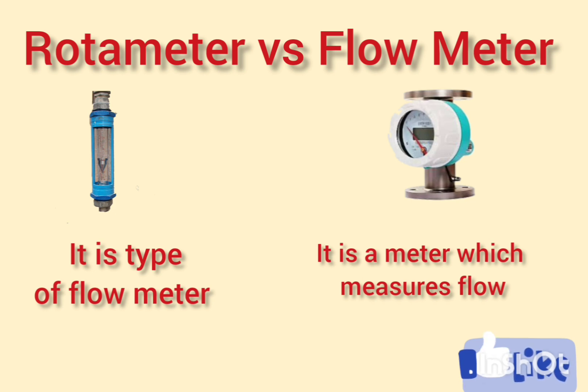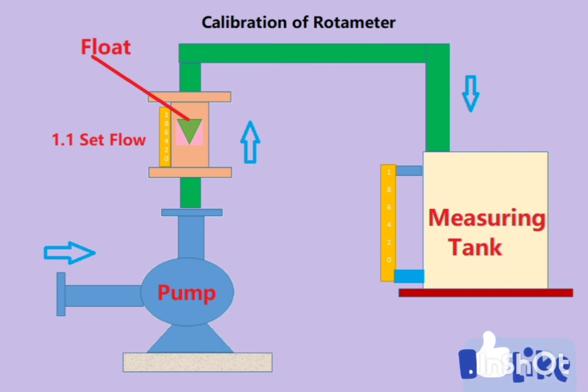This is the setup for calibration of a rotameter. You can use any kind of pump — maybe a centrifugal pump or another type. We install the rotameter we want to calibrate on the discharge side of the pump, and we need a measuring tank to measure what amount of flow is coming through.